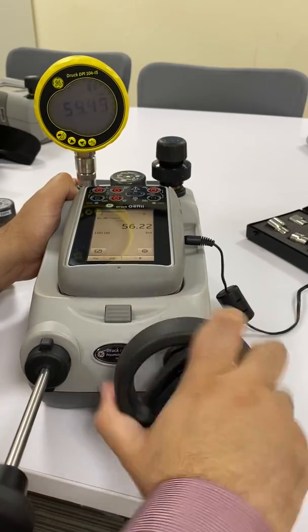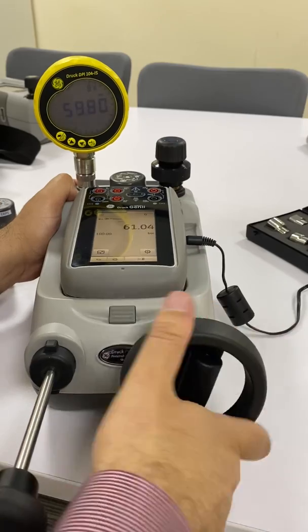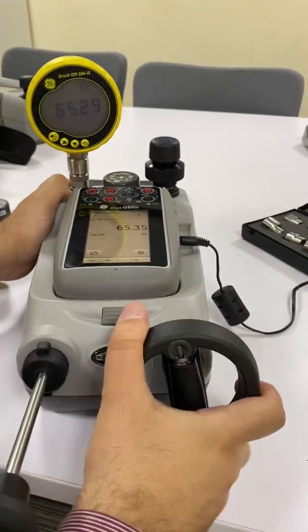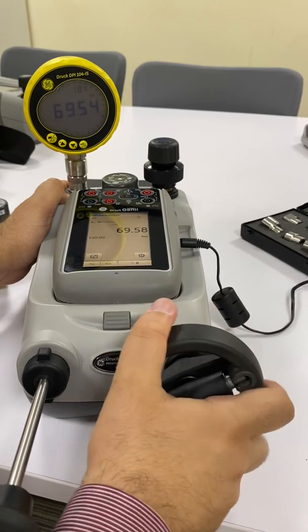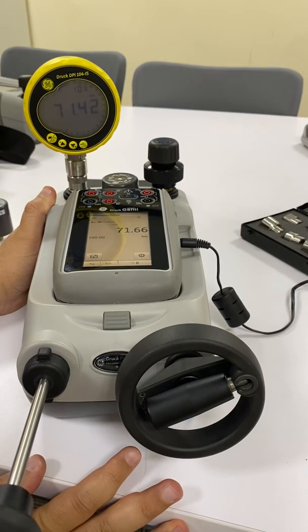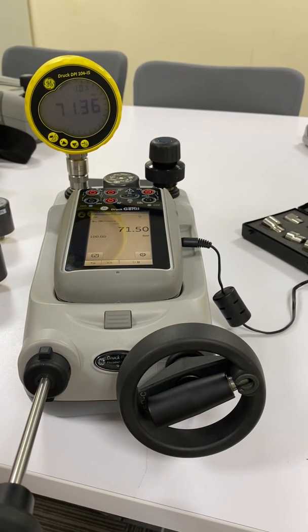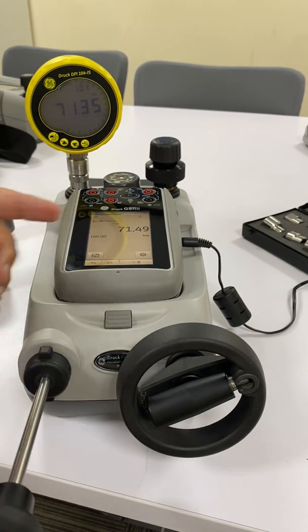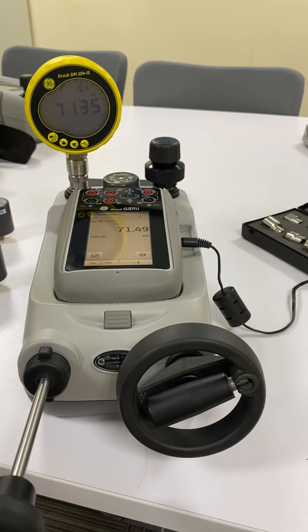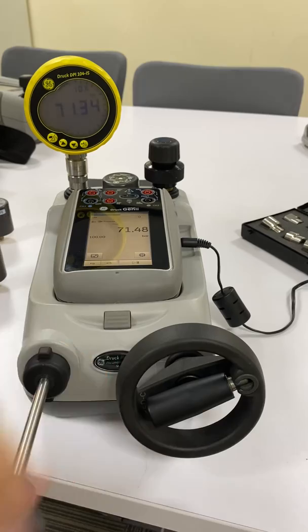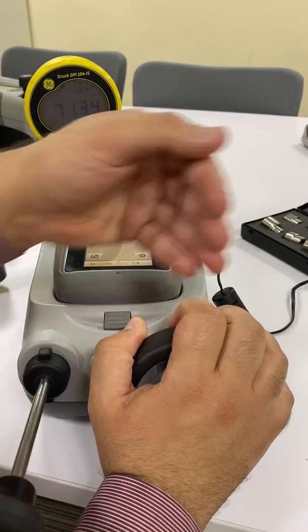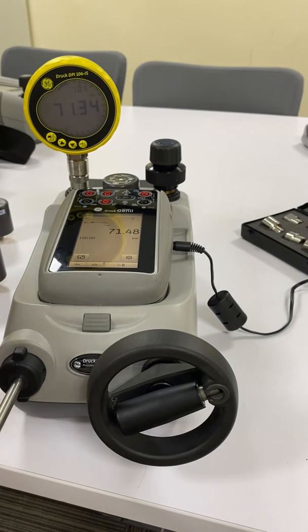50 bar, 53, 54, 56, 57, 60. So we make it triple. See, I achieved the 70 bar very easily. Now, because I put a lot of pressure inside in a very short time, as you can see, the readings are still a bit fluctuating because of the temperature effect. So the energy I put from my body to the instruments transferred inside, and it causes heat. Now it's cooling down gradually, but as you can see, the rate is not that high.